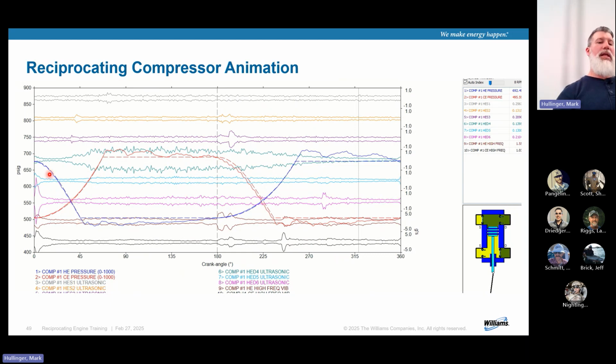These dotted lines are something we put in the software, and all they are is the engine geometry of the volumes that are in there per load step. So there's going to be a matrix of them for each cylinder, for each load step. And those are in there. Those were done before I arrived, but I've also refined the heck out of them and put them all in there. And then this is what we verify with the Windrock and the resonance: when we read this, we have indisputable evidence that our calculation on those blue screens is correct. Because gas control's trading off that information, right?